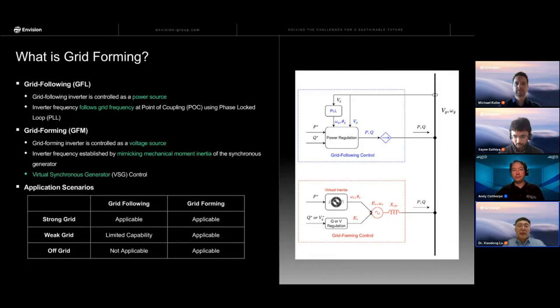And there are different grid forming control methods. The most popular ones are droop and the virtual synchronous generator. Here in Envision, we are using the VSG control. The reason we use it is because we want every critical parameter to have a clear physical meaning.